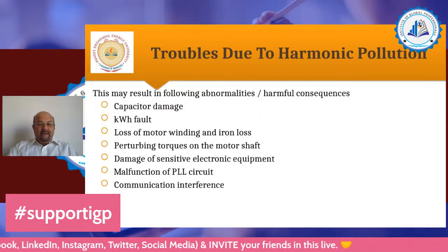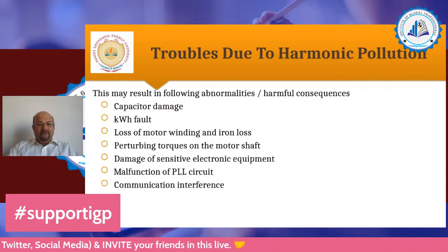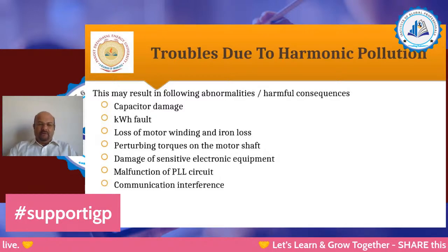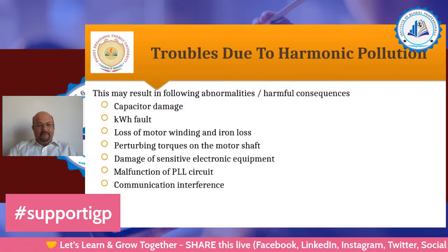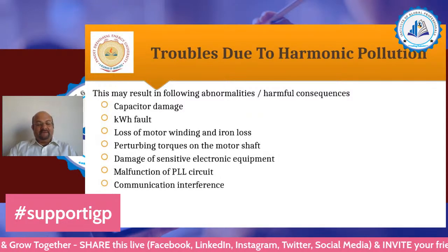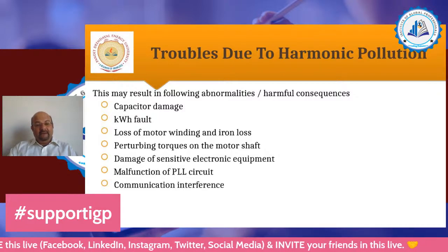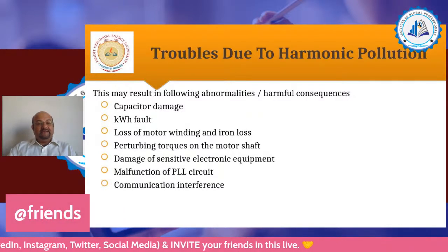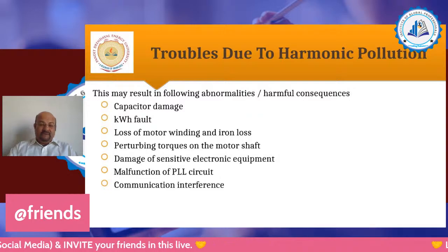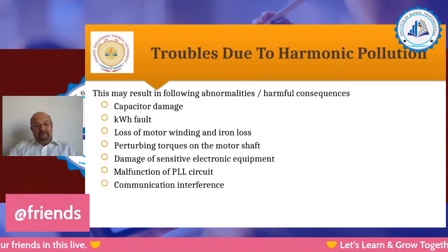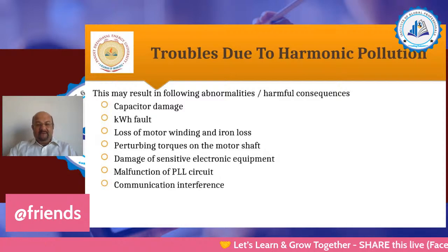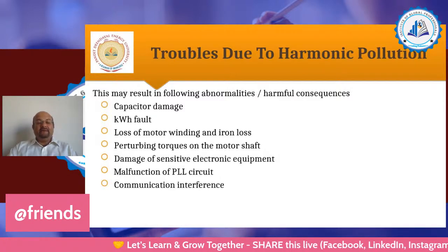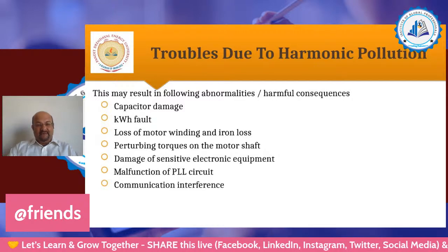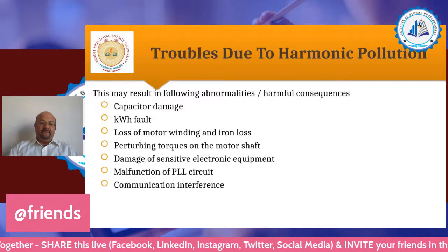Loss of motor winding and iron loss, perturbing torques on the motor shaft. Now we know that perturbing torques means thrusting torque. It is not a smooth torque prevailing on the motor shaft. How does it happen? When higher frequencies prevail in the supply, that will create a variable torque which is thrusting in nature. There are positive sequence and negative sequence components. The negative sequence will exert a reverse direction torque which will create a thrust. So these thrusting torques are known as perturbing torques on the motor shaft.